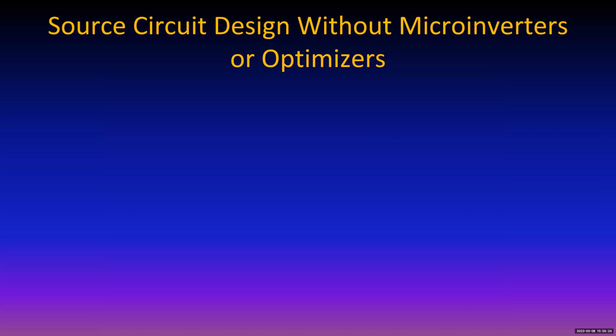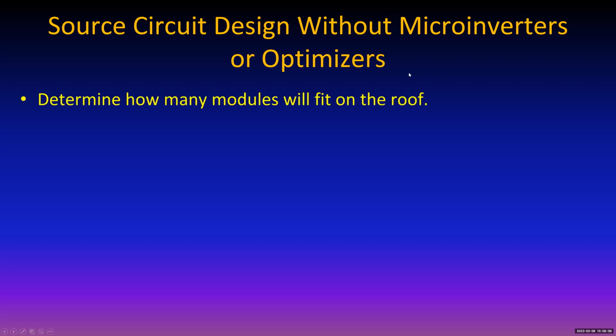Okay, let's not use microinverters or optimizers. So where would you have a situation like this? Well, normally this is what you have with the big systems. You get up to a megawatt or something, it's probably going to be a ground mount, or even a roof mount on a flat roof without any shading, and all of the modules can be strung out in strings that have the same exposure. So you don't need the fancy stuff. You don't need the microinverters or the optimizers, because your modules aren't pointing in different directions, or clouds are shading, or trees are there, or anything like that. So a quick run through how you would do it that way.